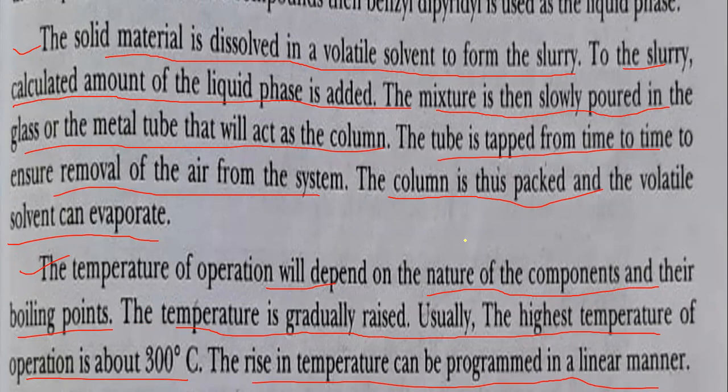Whatever temperature we are going to use totally depends upon the nature of the sample components and their boiling points. The highest temperature of operation is about 300 degrees Celsius. The whole system is well programmed so that the temperature rises in a proper way and is maintained at a fixed point for proper resolution.